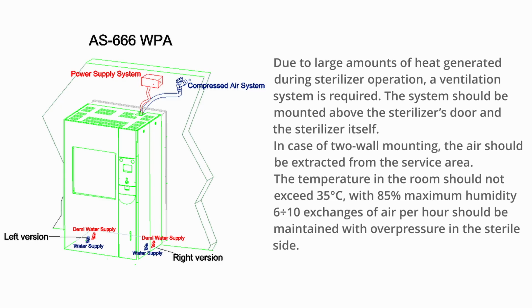Due to large amounts of heat generated during sterilizer operation, a ventilation system is required. The system should be mounted above the sterilizer's door and the sterilizer itself. In case of two-wall mounting, the air should be extracted from the service area. The temperature in the room should not exceed 35 degrees, with 85% maximum humidity, and between 6 and 10 exchanges of air per hour should be maintained with overpressure in the sterile side.